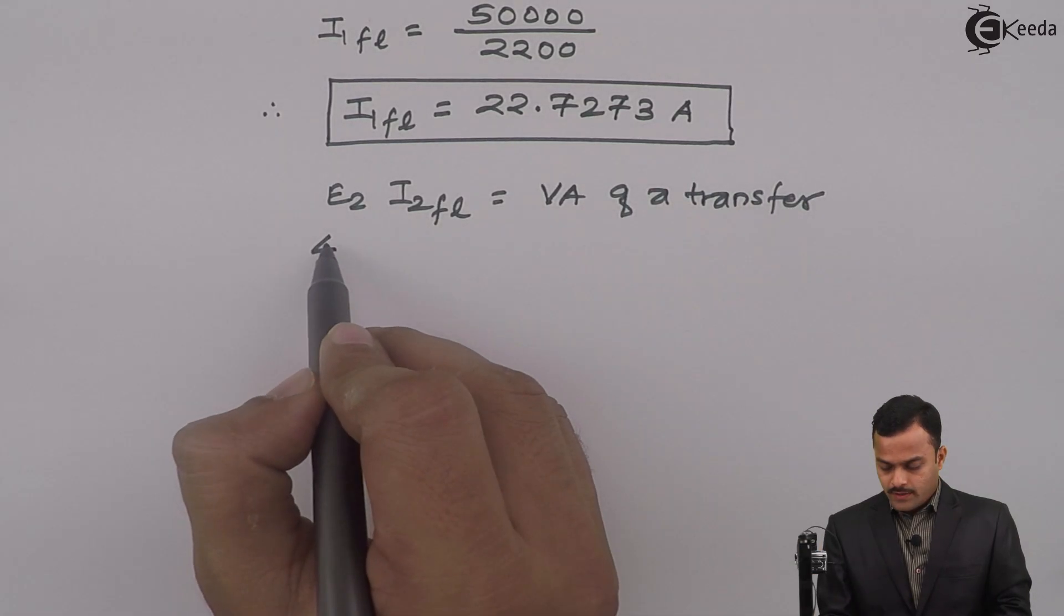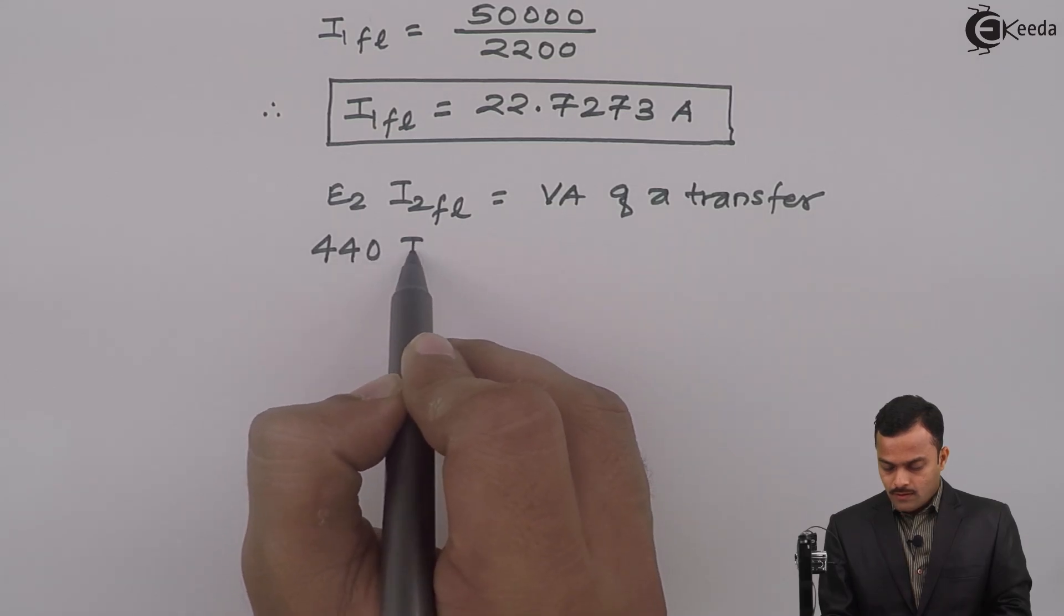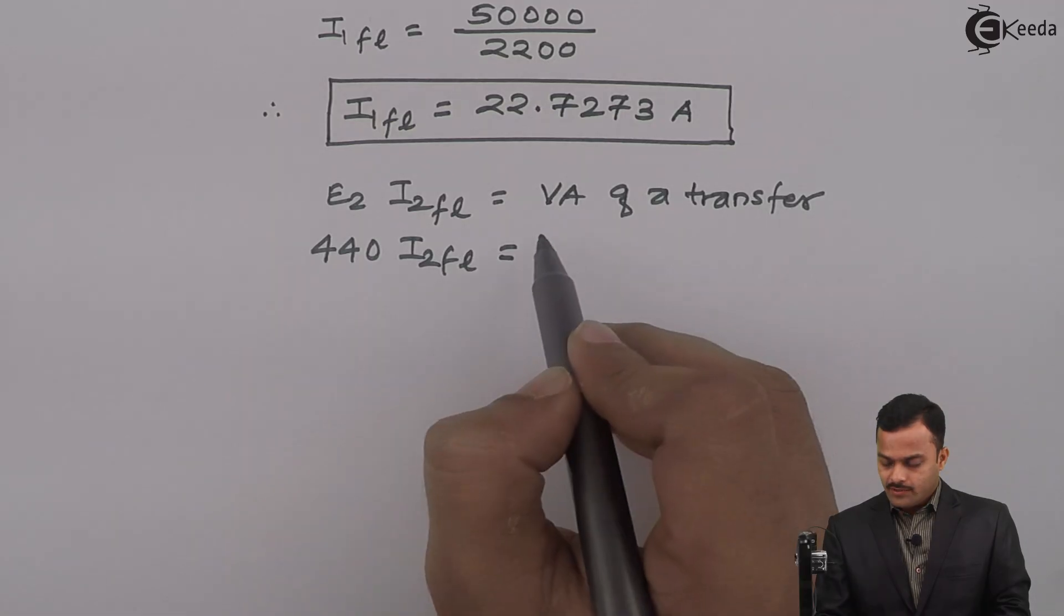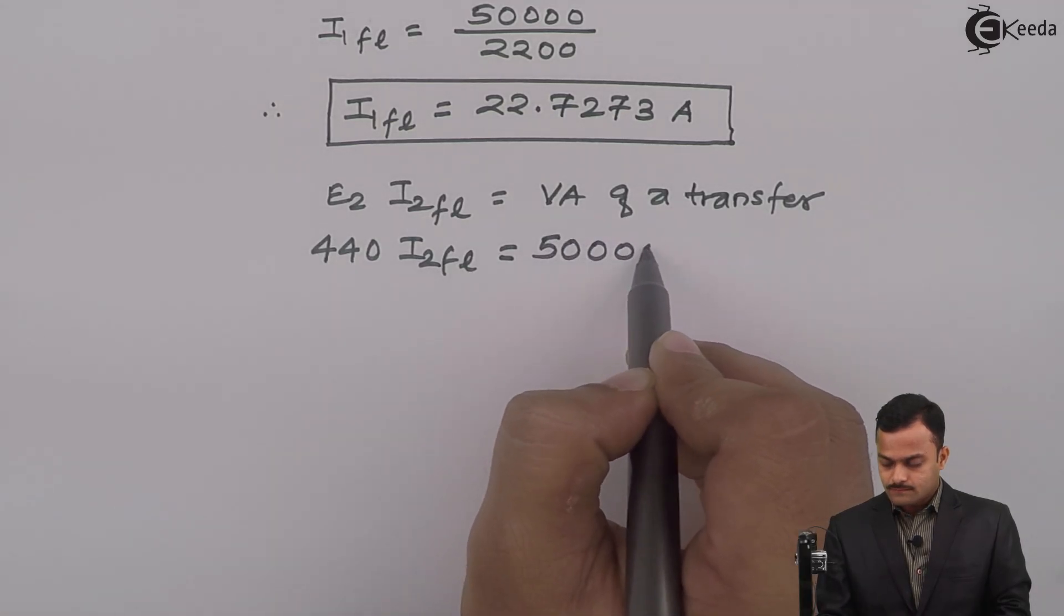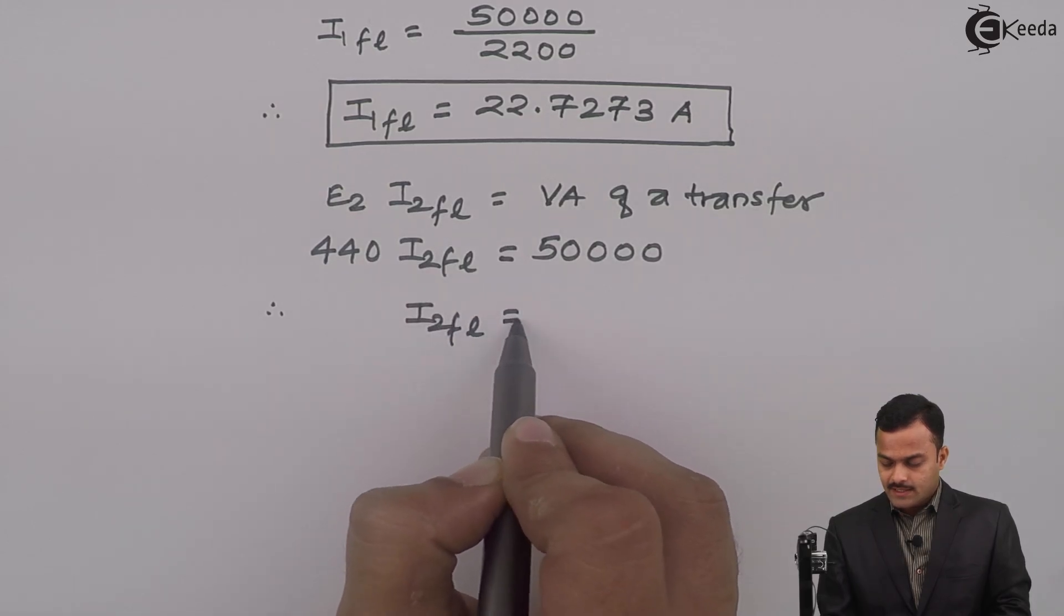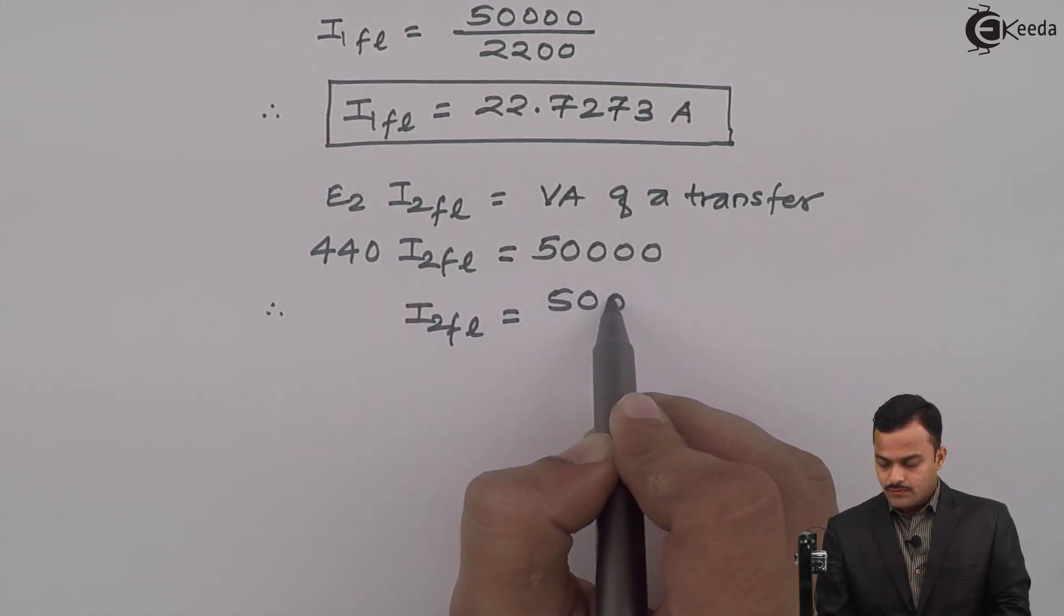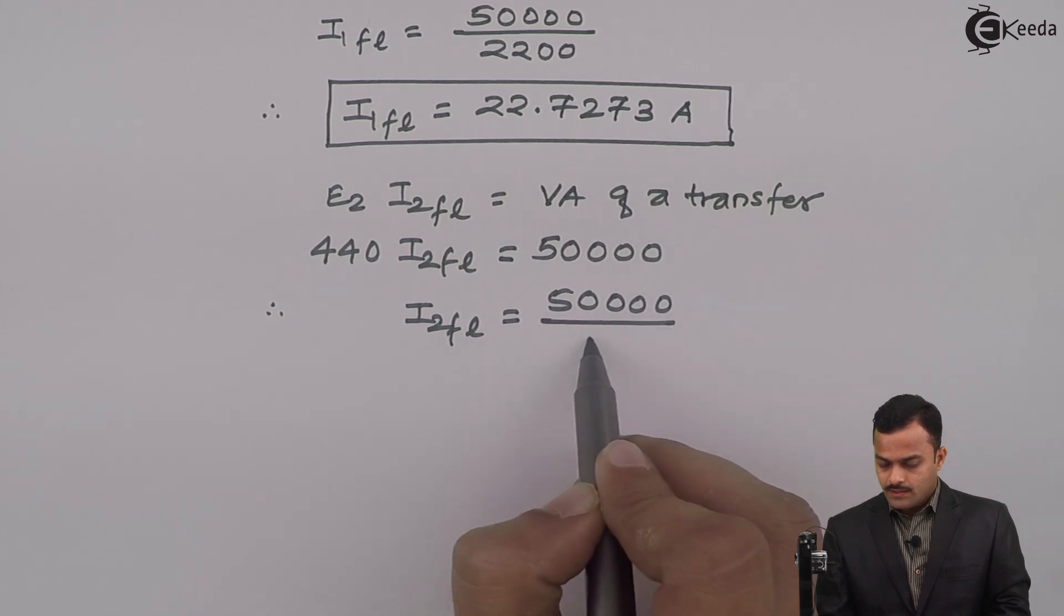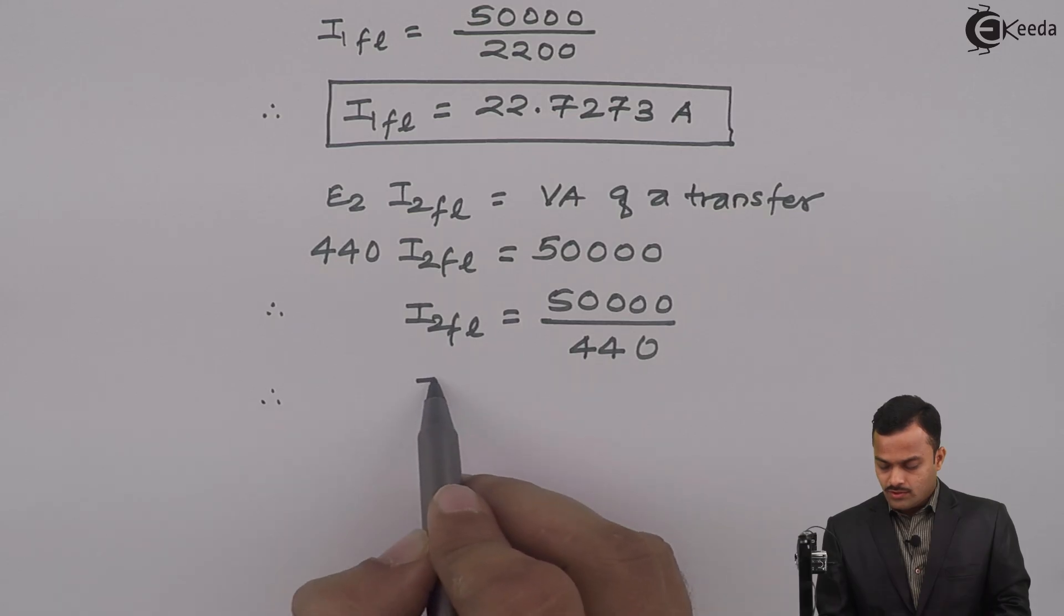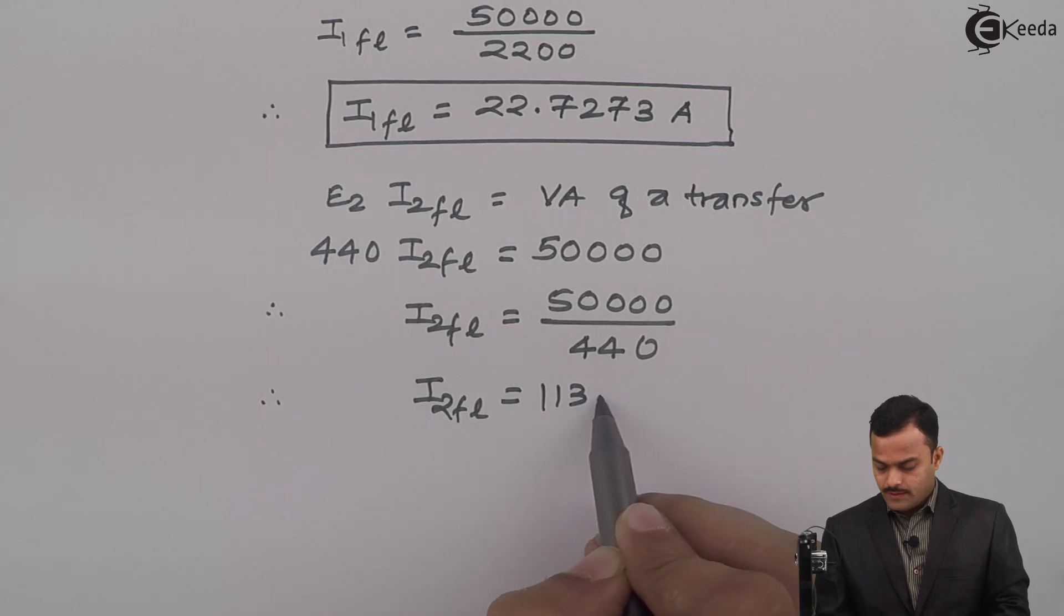E₂ is 440. I₂FL we are supposed to calculate, and VA rating of a transformer is 50,000. From this I can get rated secondary current equal to 50,000 / 440. Solution of this equation will give you I₂FL = 113.6364 ampere.